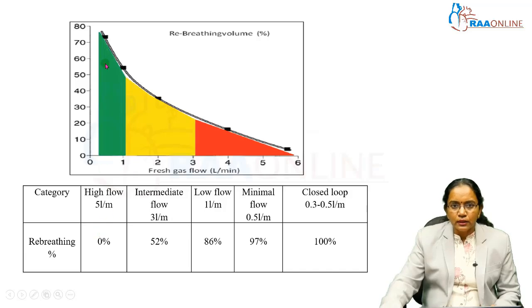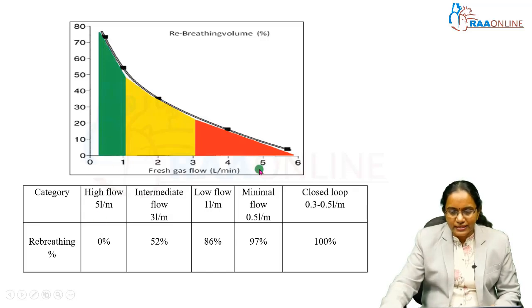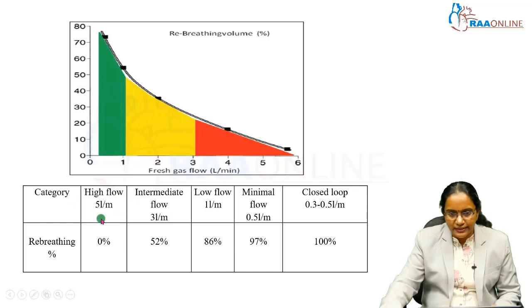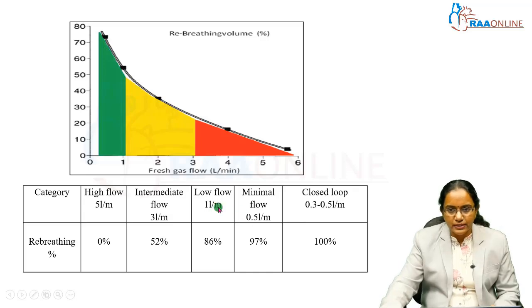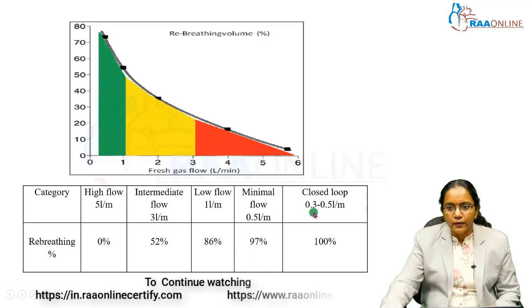This graph shows the category — whether it is high flow, intermediate flow, low flow, or minimal flow — and the percentage of re-breathing which occurs in each flow type. If it is 5 liters flow, the re-breathed volume is very low, almost 0%. As the flow decreases, the re-breathing volume increases. In high flow above 5 liters per minute, re-breathing is 0%. At intermediate flow of 3 liters per minute, the re-breathed volume is 52%. Low flow anesthesia at 1 liter per minute accounts for 86% re-breathing. Minimal flow at 0.5 liters per minute has a re-breathed fraction of around 97%, and in closed loop anesthesia where fresh gas flow is 0.3 to 0.5 liters per minute, the re-breathed fraction approaches maximum.